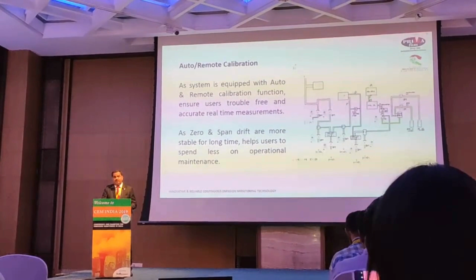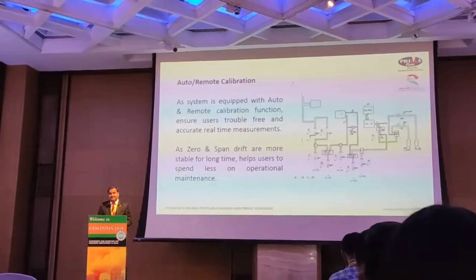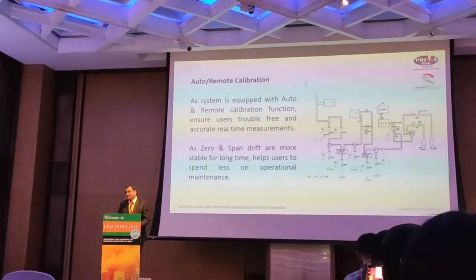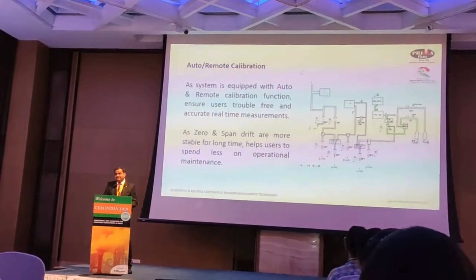While testing all this, we also incorporated auto calibration and remote calibration methodology. We made an in-house setup in our R&D department connecting not less than 6 various gas cylinders, controlled with a PLC and synchronized with the CEM system we developed. This let us automatically verify how the auto and remote calibration functioning works, and the results came out well.